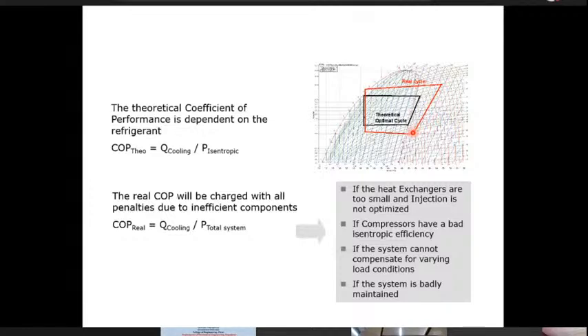So the size of the heat exchanger will depend on the delta T, the temperature difference between the medium being cooled and the refrigerant temperature. So this you can see over here, the difference between the red and the black. And again, here to reject heat to the environment, we need to take it to a temperature higher. So in the condenser, the refrigerant temperature has to be higher than the temperature to which we want to reject heat, whether it is a water-cooled condenser or an air-cooled condenser.